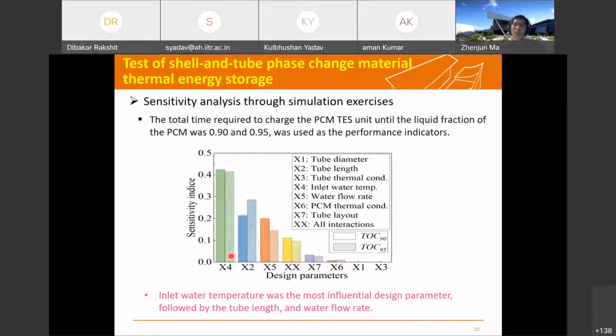If you increase it, this temperature difference will decrease. Based on these observations, we did a sensitivity analysis to look at the major parameters influencing the design of this thermal energy storage. We used the performance indicator of the total time required to charge the PCM thermal storage to a liquid fraction of 90% and 95%, meaning 90% or 95% of the PCM is changed from solid phase to liquid phase.